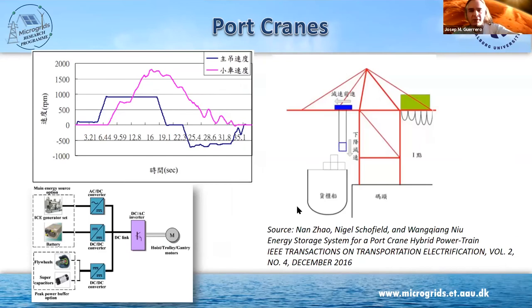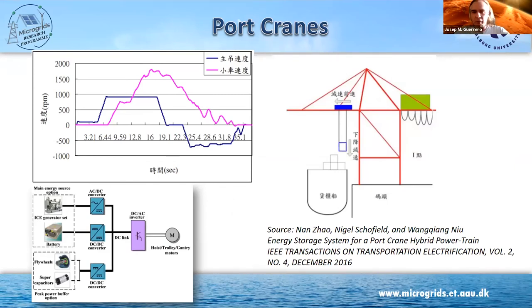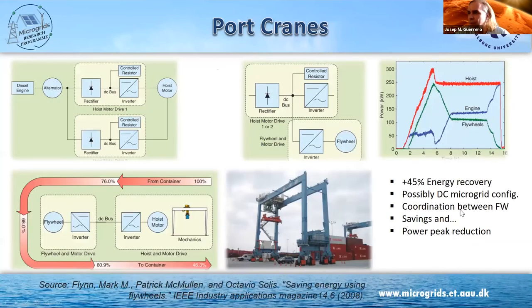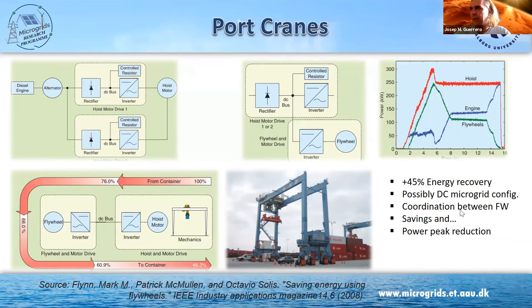Another challenge point are the cranes. Some cranes are still burning diesel, which is an important point of CO2 emissions to reduce in the next years. We are substituting diesel generators with connections to the main electricity point. On the cranes, when you need to lift up a container you inject energy, but when you lower those containers you can convert the motor to a generator — instead of burning electricity in dummy resistors, you can reuse it. According to the latest studies, you can get between 40 and 50 percent of energy recovery, which reduces energy consumption in the port and also reduces the peak electricity demand.